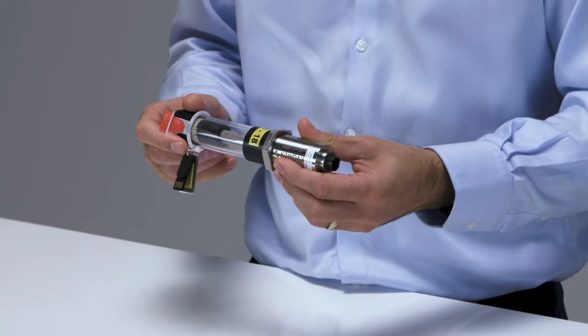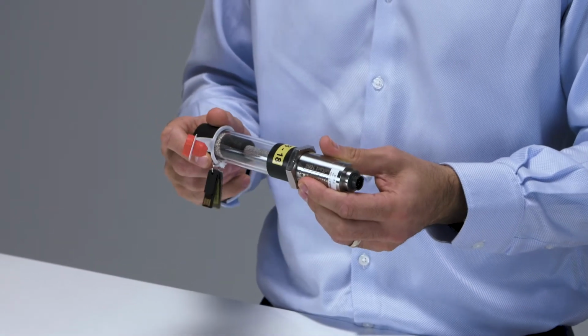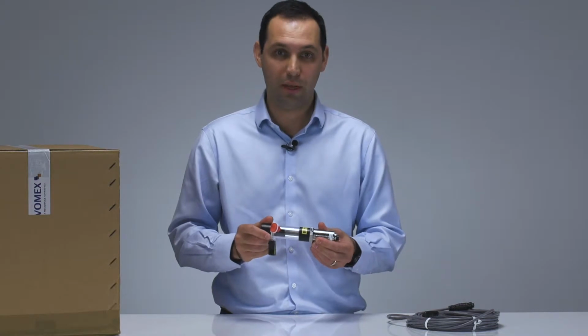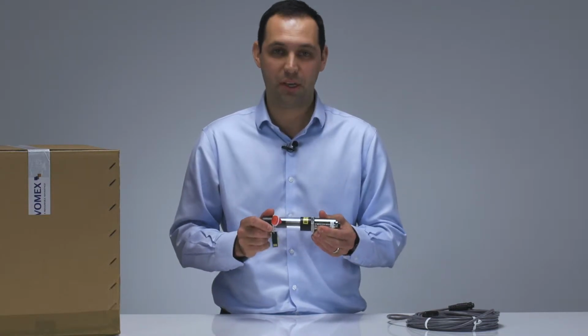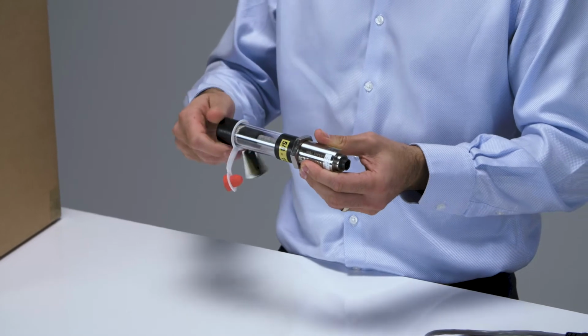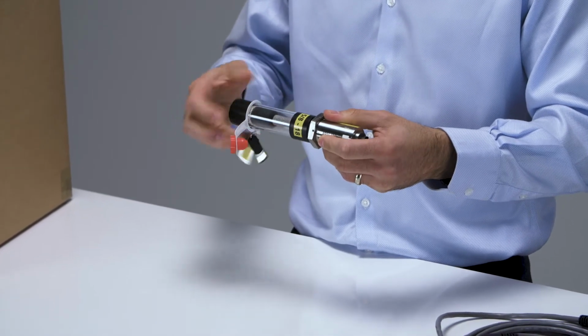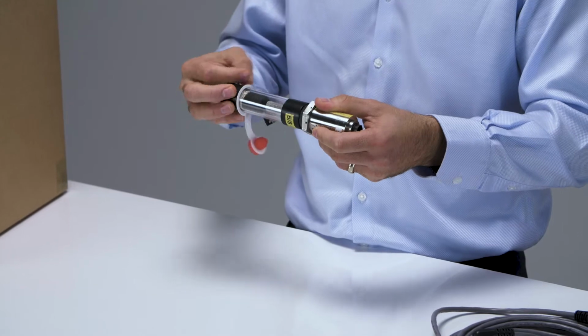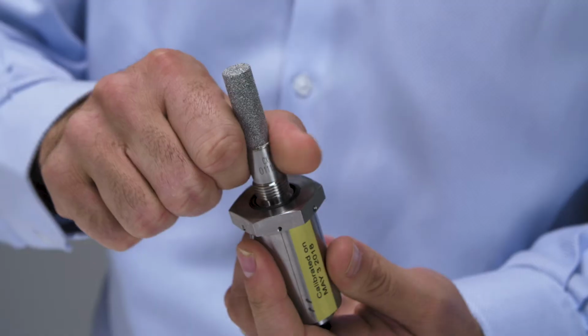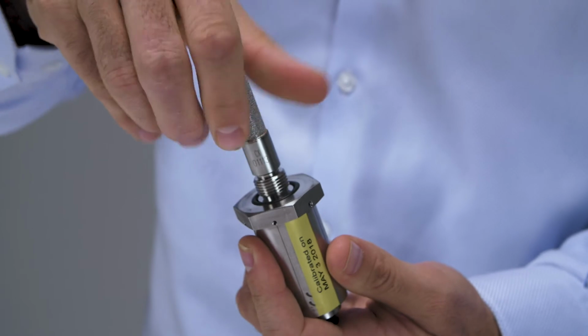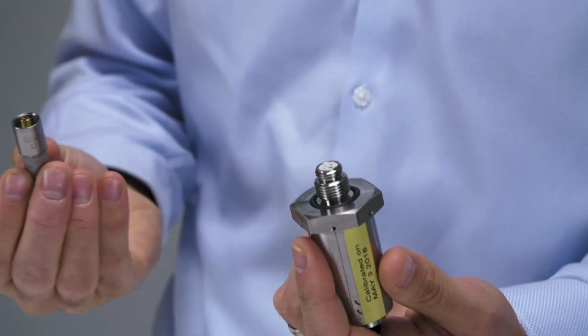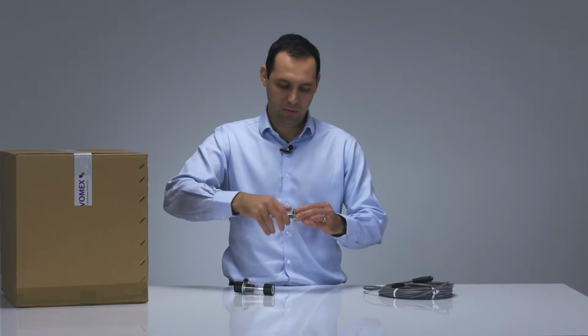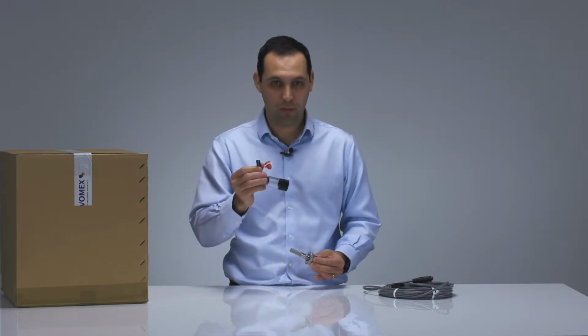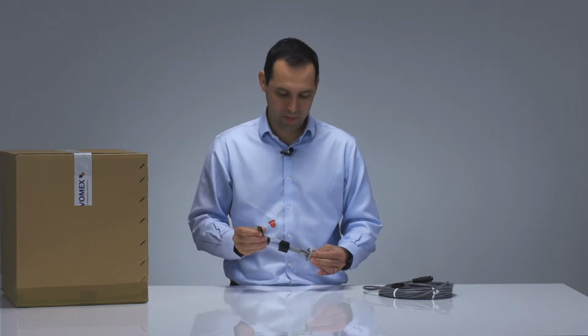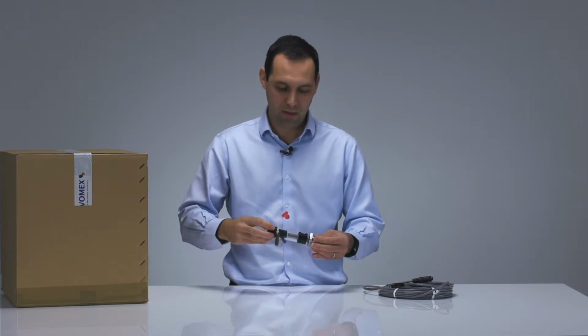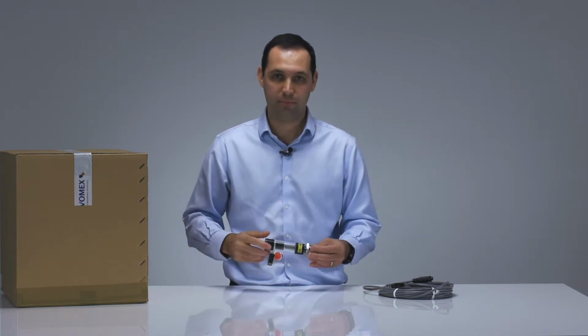One of the key features of the AquaXact 1688 is the ability to field replace the sensor tip, resulting in minimal downtime. The operation is very simple. The sensor needs to be removed from the process. The tip can then be simply unscrewed, replaced, and the calibration data stored on the attached USB stick can be added to the analyzer for uploading onto the sensor.